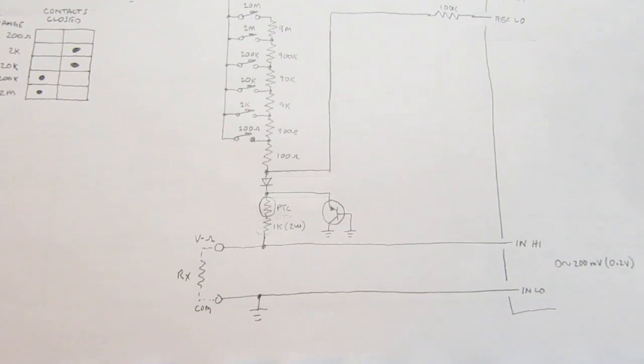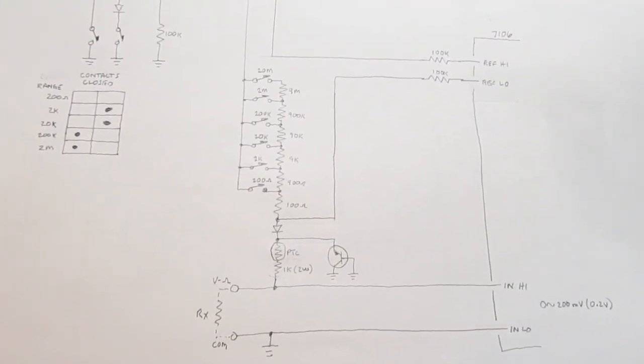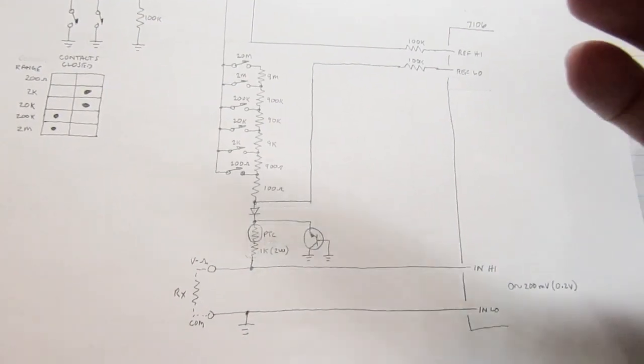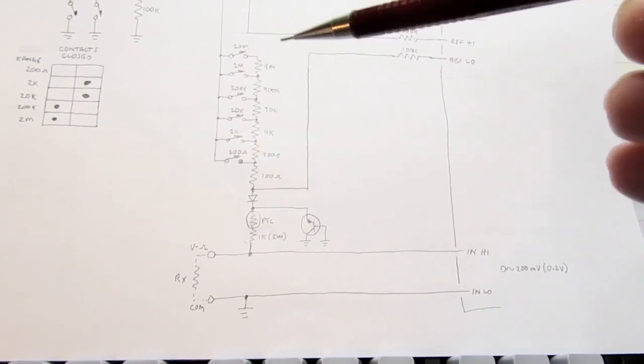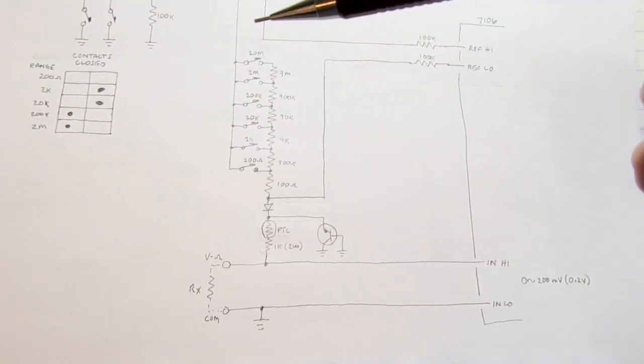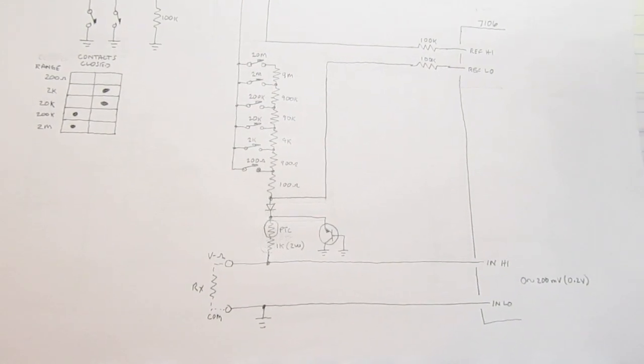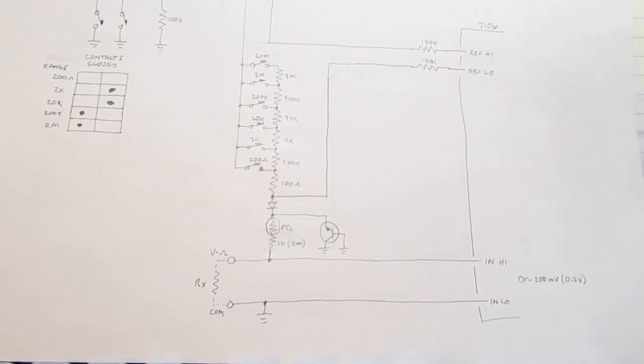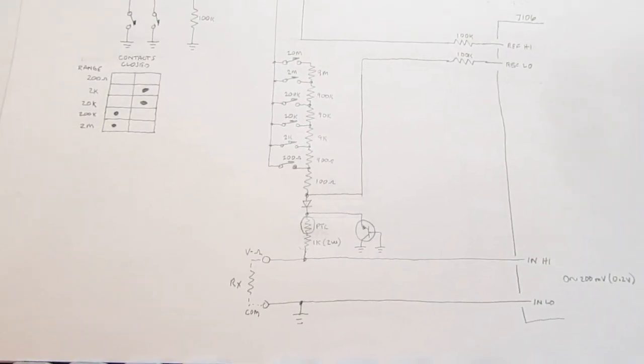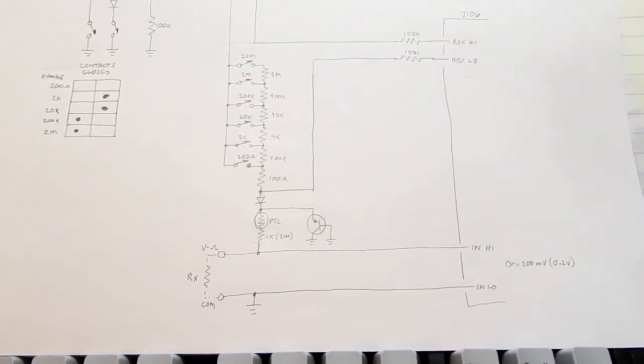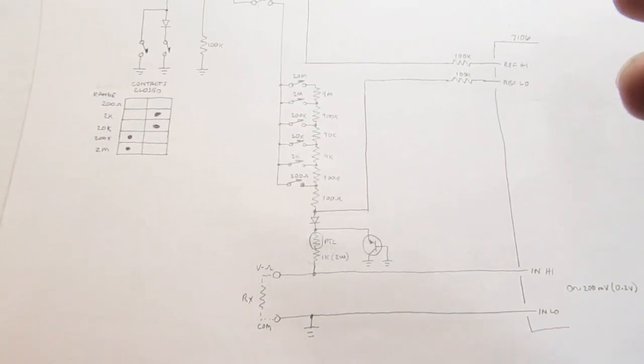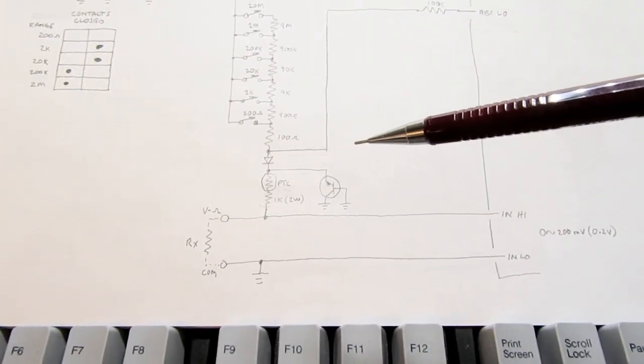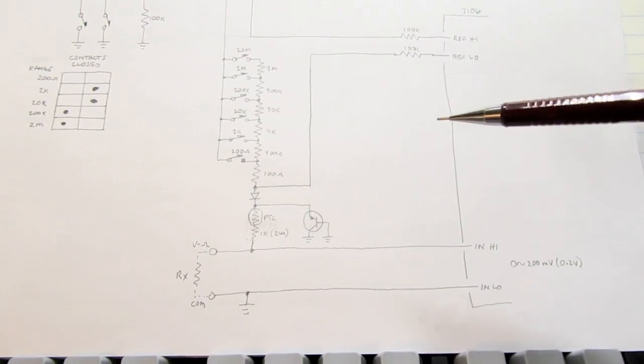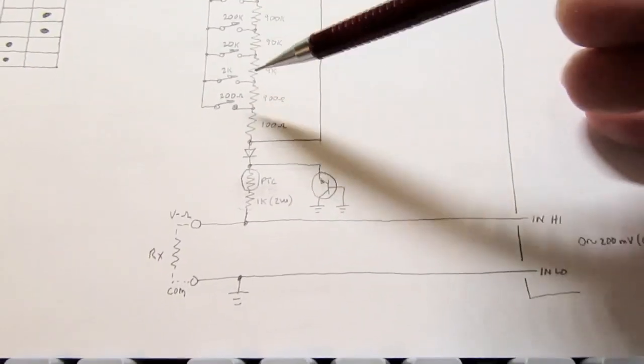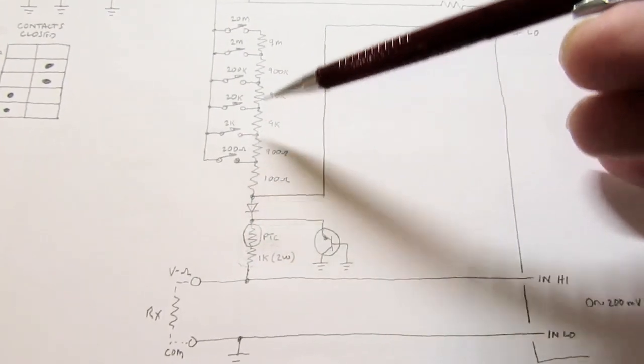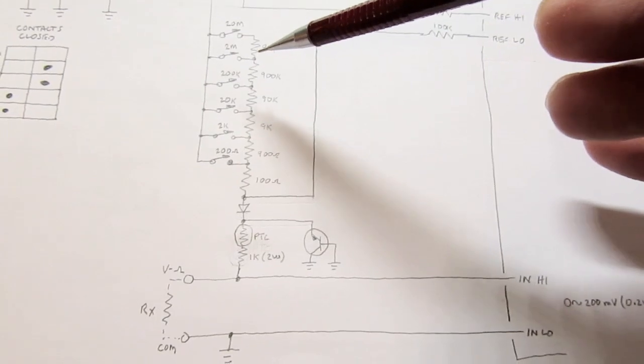It's superior to the other scheme of using a precision constant current source and then measuring the voltage across it, because that system cannot track drift. If your precision constant current source isn't that constant, if it has any small differences in it, then that will be reflected in decreased accuracy of your ohms measuring function. But with this very simple scheme, it's impervious to pretty much any change in the circuit, except for very small changes in these resistors, of course. These are precision resistors, and they shouldn't change much over time or with temperature.